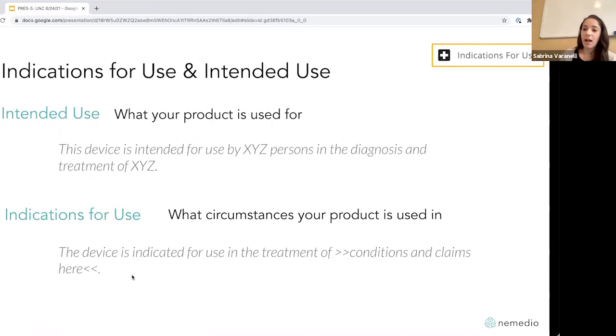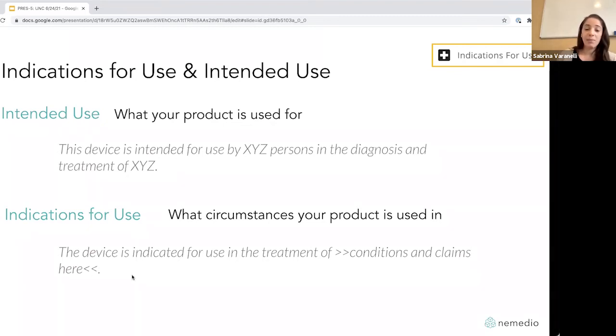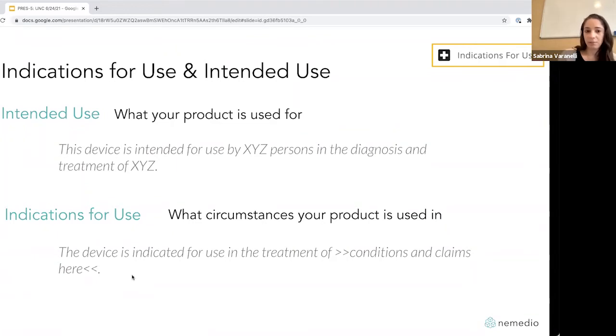You as a company at your early stage — you had an idea to build this product, you know why you're building it. You don't need to write it perfectly, but if you write out your indications for use — whether in a Google doc or using the Nemedio system — this is a really big step in getting the initial set of documentation you need to be on the right path for transitioning to full compliance.